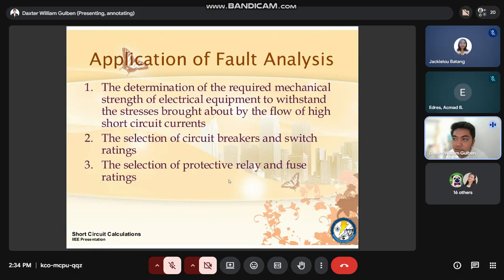And also the fuse ratings, no, kining mga cut out fuse, basically makita nato na sa every distribution transformer sa atong linya. Every time nga naay lateral connection sa atong three phase, naay na siya fuse. The same thing sa atong transmission system, naa pod mga cut out fuse sa ilahang mga large consumers connected directly sa transmission system. So how do we determine the rating of that fuse? It will be based on the fault level or fault calculations sa atong short circuit analysis.